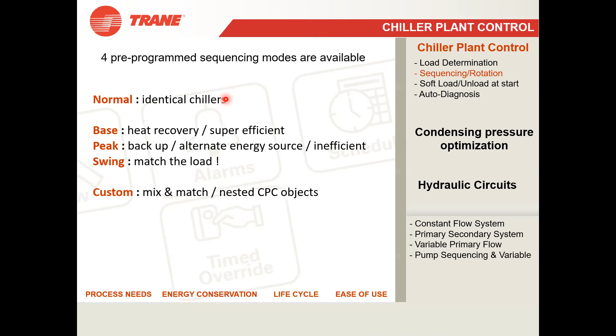These are the pre-programmed sequencing modes available in the CPC. In normal mode, all the chillers can gradually increase the load since every chiller has the same efficiency, so there's no problem. You can set it in normal mode, and all the chillers will run normally and equally.